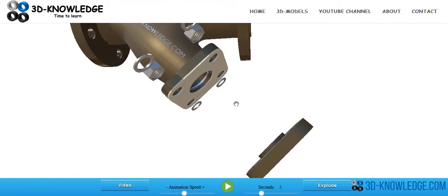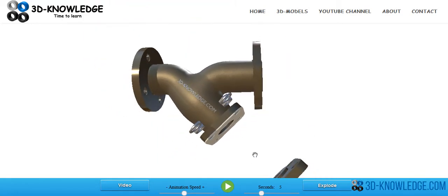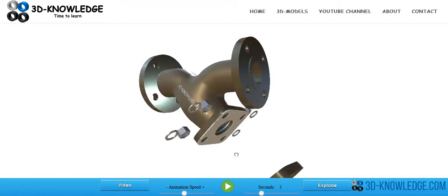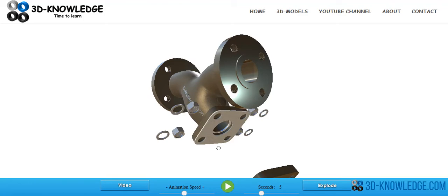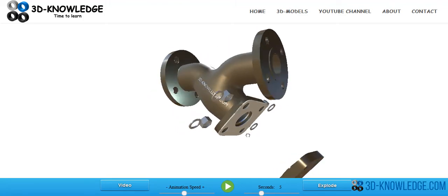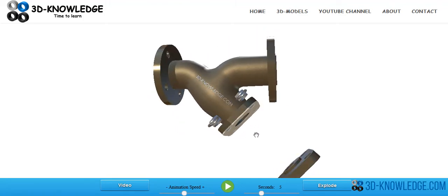Just remember also with the gasket that when you're installing the gasket, you want to cross tighten the bolts. You don't want to just clamp two of the bolts together, because the bolts that have been clamped together will squeeze the gasket, and they'll tend to either crush it so that the seal doesn't form properly, or you'll create a crease in the gasket, and this is a really good place for the fluid or the flowing medium to leak out.